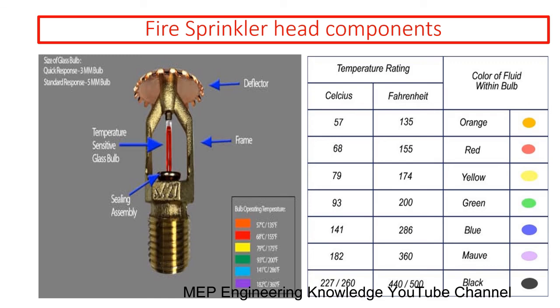For example, if we need to operate a sprinkler at 57 degrees centigrade, then you need to select the orange color sprinkler bulb. If you want to operate the sprinkler system at 68 degrees centigrade, then you need to go with red color. Similarly, for 79 degree operation, you need to select yellow. For 93 degrees centigrade, you need to opt for green color. For 141 degrees centigrade, you need to select blue color. For 182 degrees centigrade, you need to select mauve, and for 227 or 260 degrees centigrade, you need to select black color. Depending upon the area usage, you have to select the color of the sprinkler. Sprinkler bulb color has a strong reason.